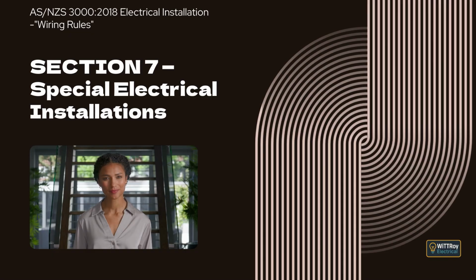Clause 7.2.6.2.1 Types of wiring systems for fire detection and alarm systems. This clause explains that wiring systems supplying fire detection and alarm systems must comply with ASNZS 3013 and use a wiring system classification specified by the relevant installation standard. Where no wiring system classification is specified, the wiring must be capable of maintaining supply when exposed to fire or mechanical damage, or must maintain supply when exposed to fire while also being protected against mechanical damage. This protection may be achieved by installing the wiring in an effective enclosure or locating it where mechanical damage will not occur.